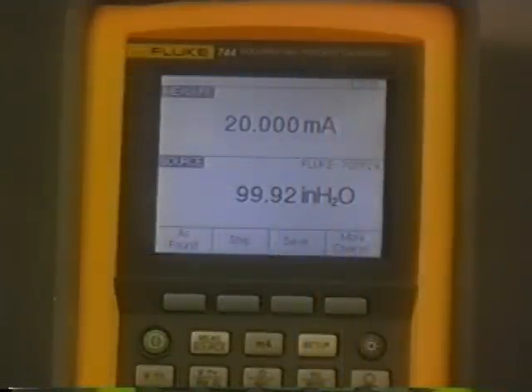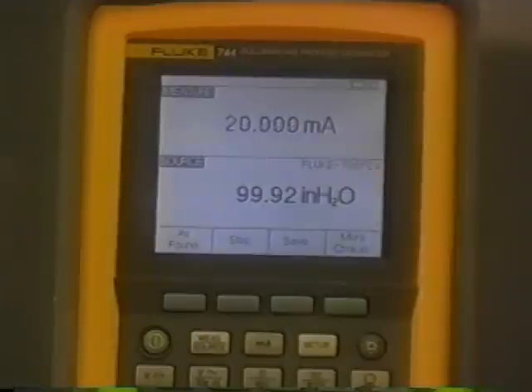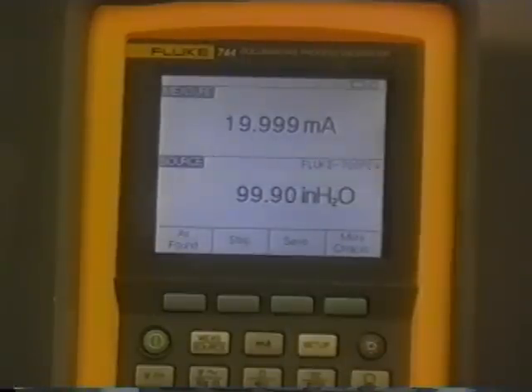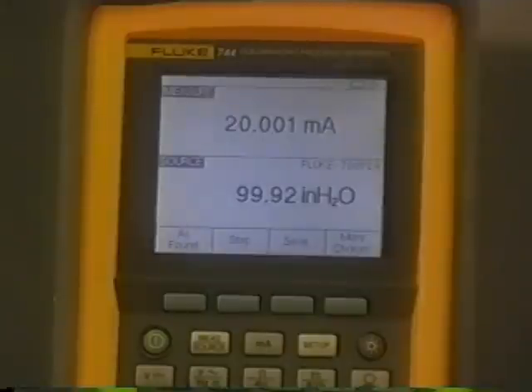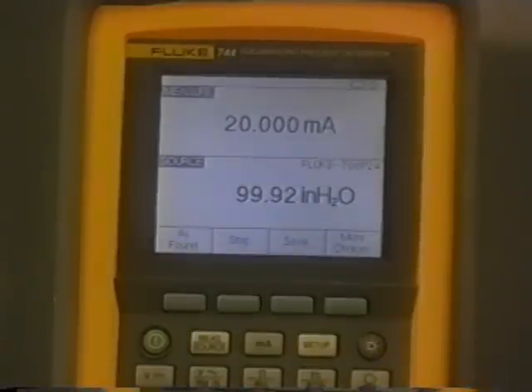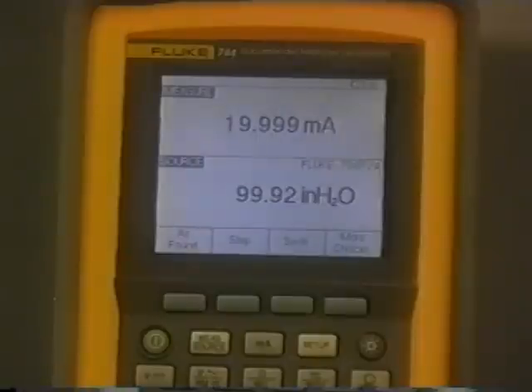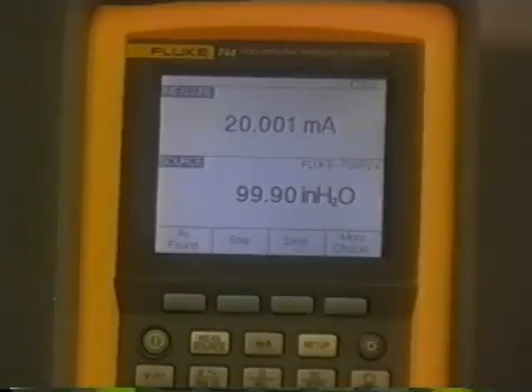As you can see, when you reach 100%, the transmitter output should be 20 milliamps, if everything's done correctly. At this point, we would start to go downscale by 10% increments as well. The reason being is to show whether there's any hysteresis in the device or not.